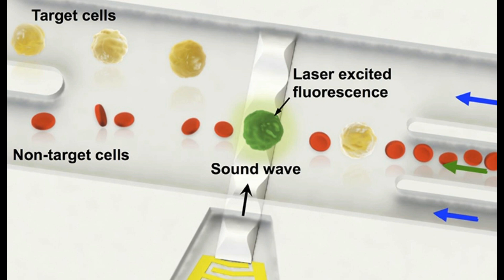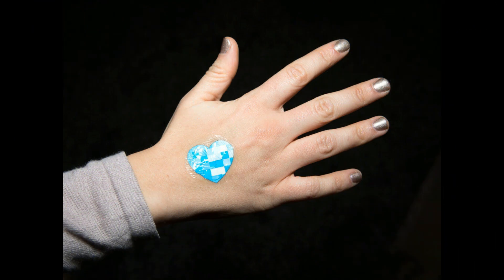Compared to conventional FACS systems, the merit of this cell sorting technology includes a substantially simplified sorting mechanism that shrinks the instrument's size, reduces its complexity, and substantially lowers its cost. Not only that, but it also enables more accurate single-cell level sorting and leaves no damage on targeting cells because sound waves are much gentler than electric fields while using the conventional FACS systems.